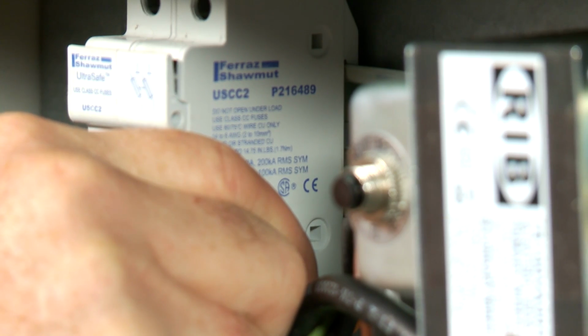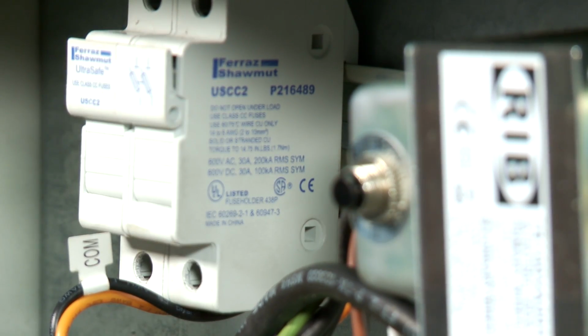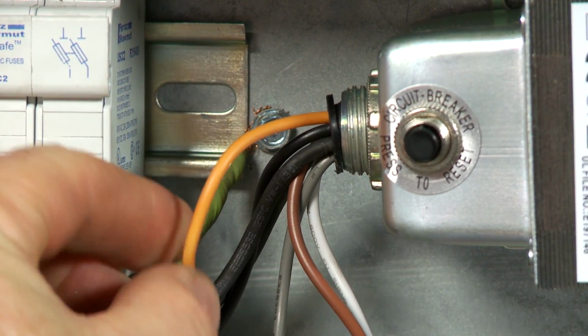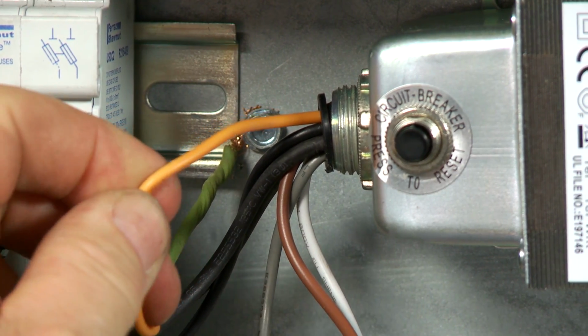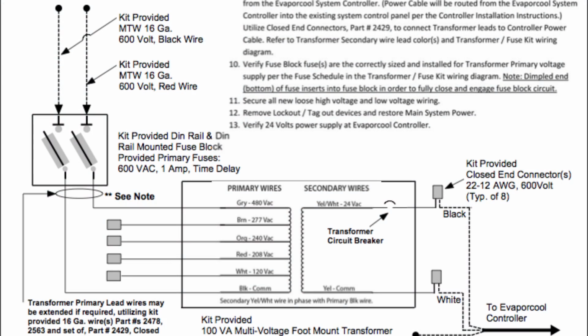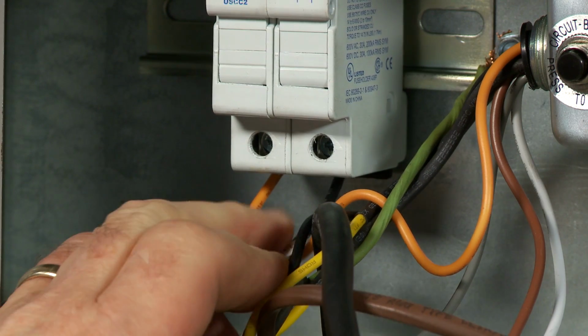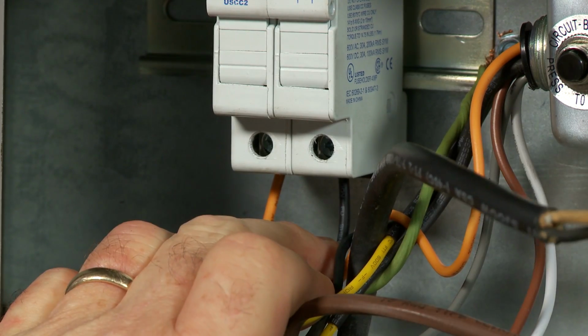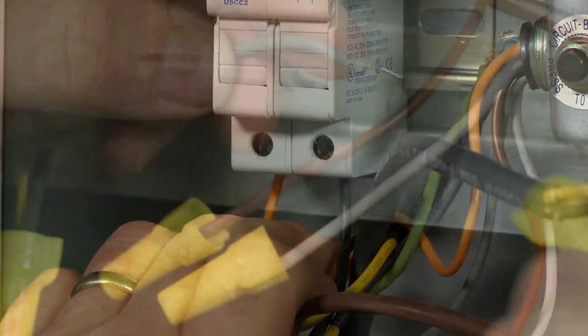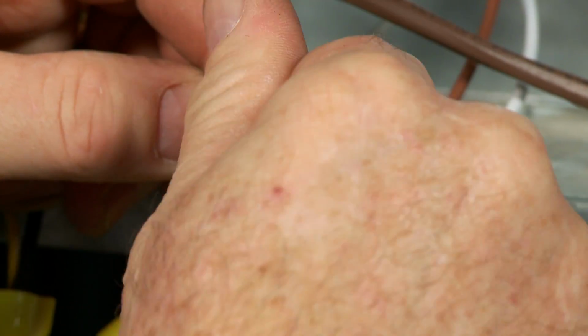Using the wiring diagram included with the fuse kit, identify the color of the primary wire that matches the main unit voltage. Connect the appropriate transformer primary lead to one of the openings on the bottom of the fuse block and connect the black common wire to the other opening on the bottom of the fuse block. Using the included wire nuts, cap off any unused primary transformer wire leads.